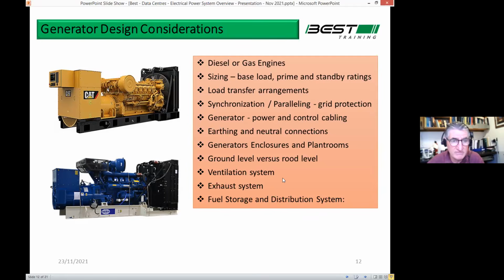The exhaust system: you can see these data centers now, they're building them all over the place, and they're instantly recognized by the generator flues, the big polished stainless steel flues. You see them popping up over the ridge of the building. They look like warehouses, and all of a sudden you see these shiny chrome flues up the side of the building, and it's a dead giveaway that it's a data center when you see that. So where you put the exhaust system, how you get up to the building, and then most importantly, fuel storage. So your diesel generator has to have typically 36, 48 hours storage of diesel, which is a massive amount of diesel to store on the site.